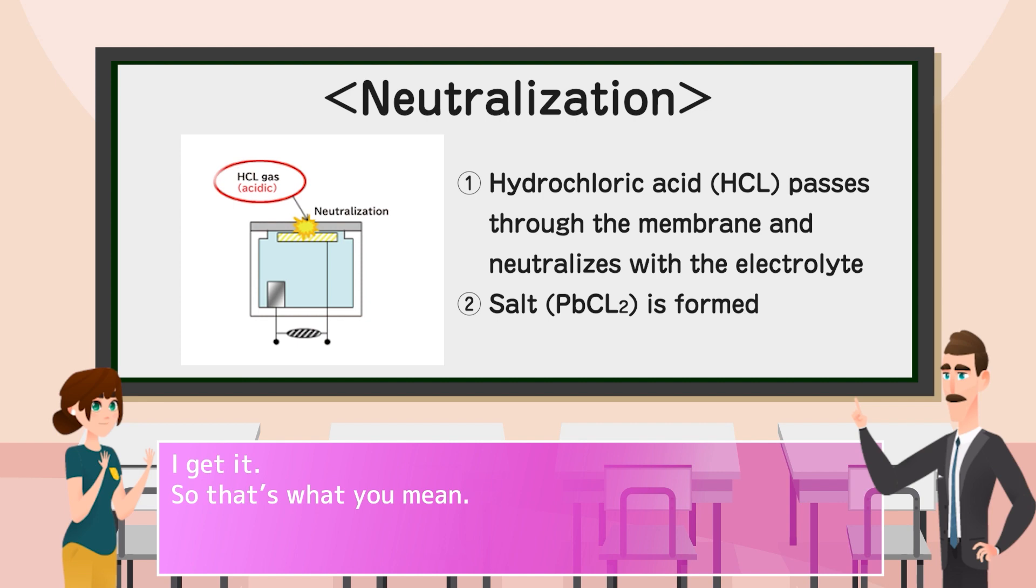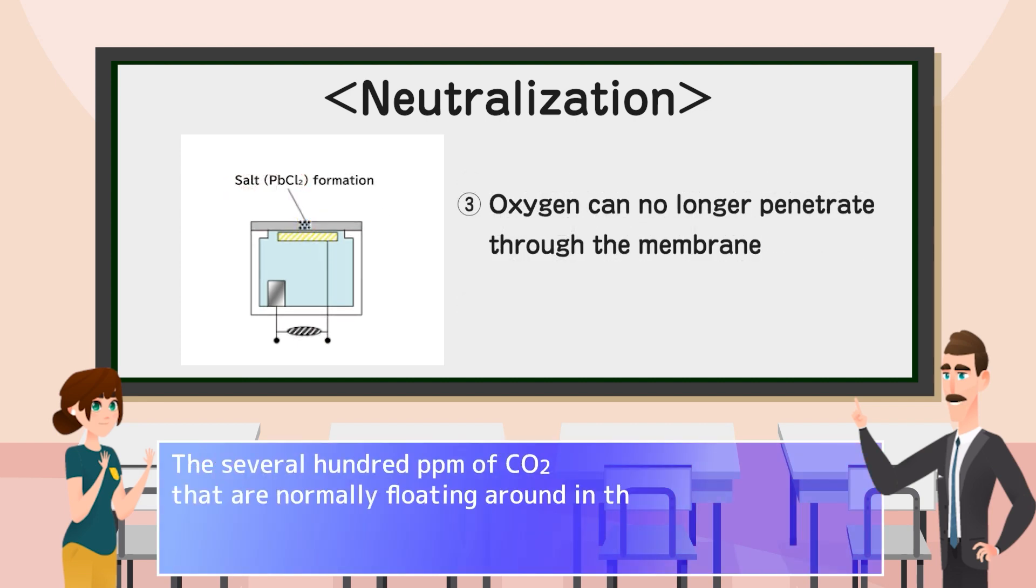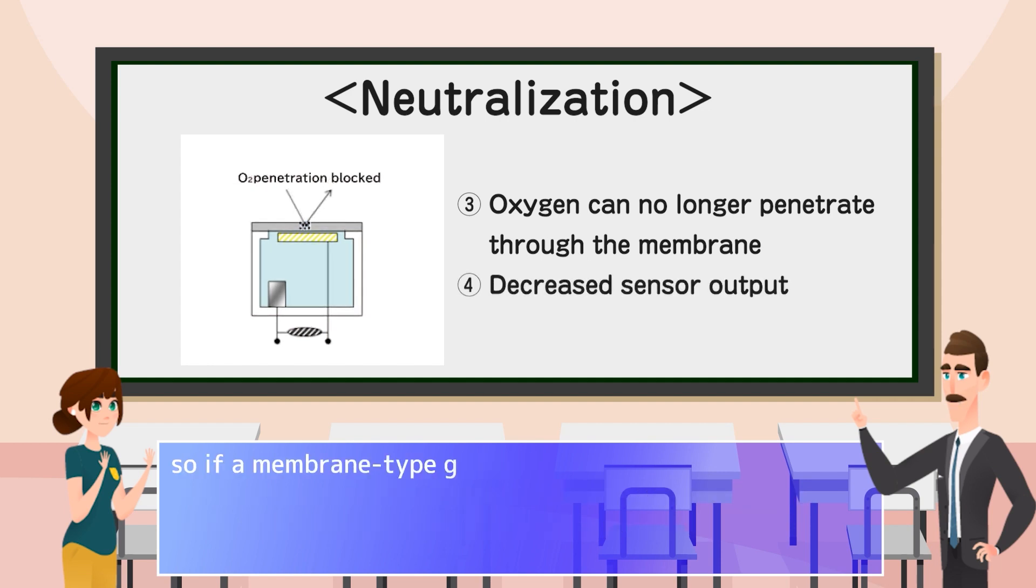I get it. So that's what you mean. The several hundred ppm of CO2 that are normally floating around in the atmosphere are, while weak, actually gas with acidic properties. So if a membrane-type galvanic cell method sensor were to be used in a location where the concentration of CO2 is consistently several dozen percent, the sensor sensitivity would decrease within a few months.